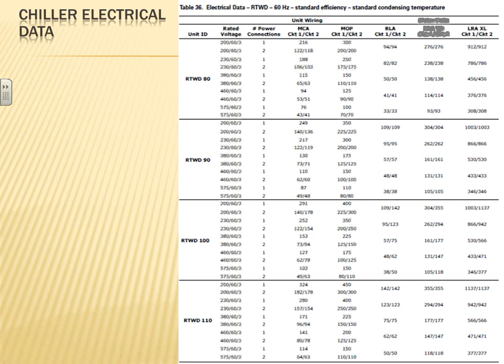I've been successful with that in the past, but you have to call the rep and say, we need the rest of the information, because the cut sheet doesn't give it all. If it's small, it might not make any difference, but if it's a big unit, it can make a huge difference. I've had to reverse engineer it out of the MCA, and if it came out exact, then I was happy, and if it didn't come out exact, I was still not happy, and I still told them they had to come up with a number from the rep.